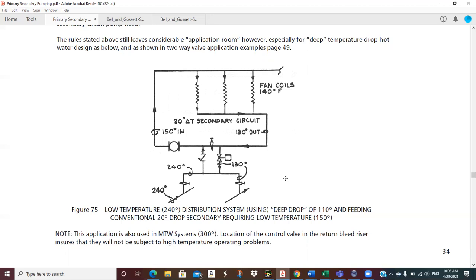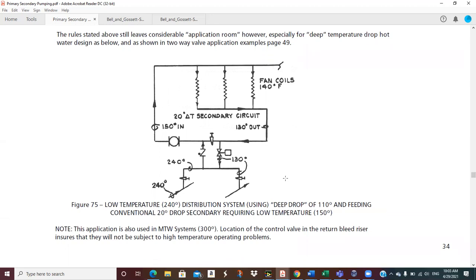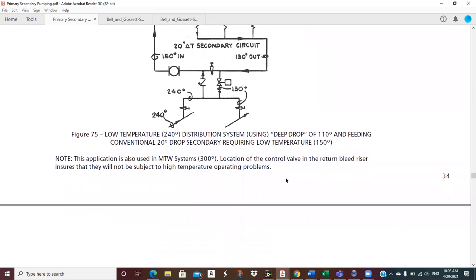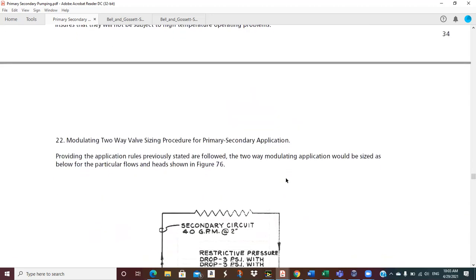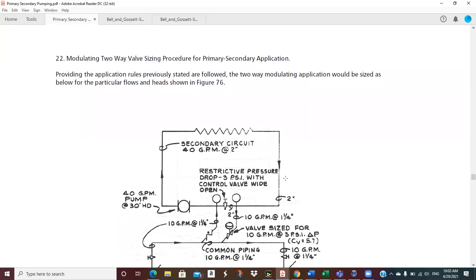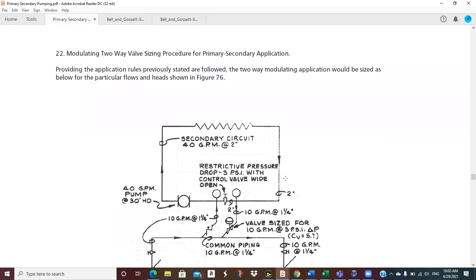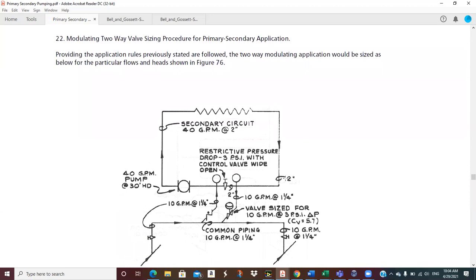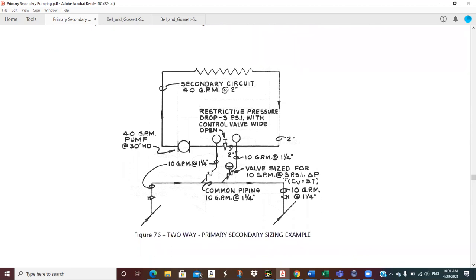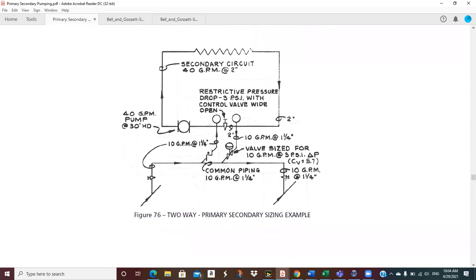Let's see. This is low temperature water. He makes a note that 300-degree water temperature supply systems would be medium temperature water, and that would probably even work better. Okay, modulating two-way valve. Let's look at sizing procedures for the two-way valve. Let's just take a look at what we've got here.